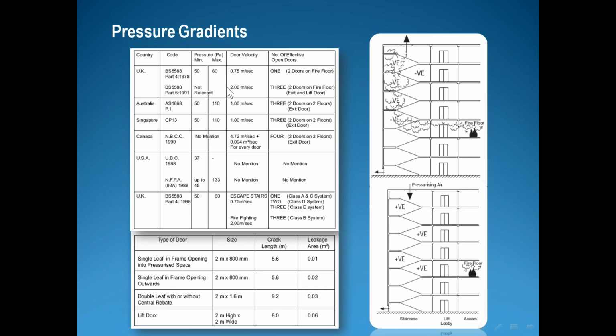Here, what is the required pressurization according to different standards? The British standard, the Australian one, Singapore, Canada, USA, this is the Uniform Building Code, the NFPA, and finally, Part 4 of the British standard, which is a little bit old but is still the same, except for high-rise buildings. And this is the leakage for the standard doors. What is the leakage area and the crack? So you can calculate the losses of air. You will lose it here, and you can consider this door will be normally open all the time during evacuation, with a discharge of pressurized air at about 1.5 meters per second.